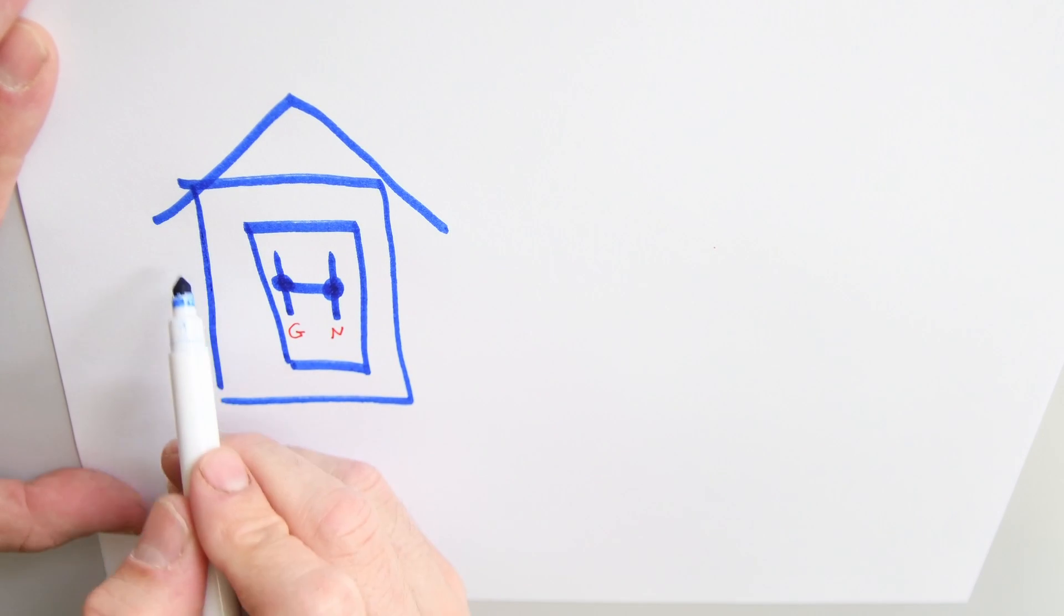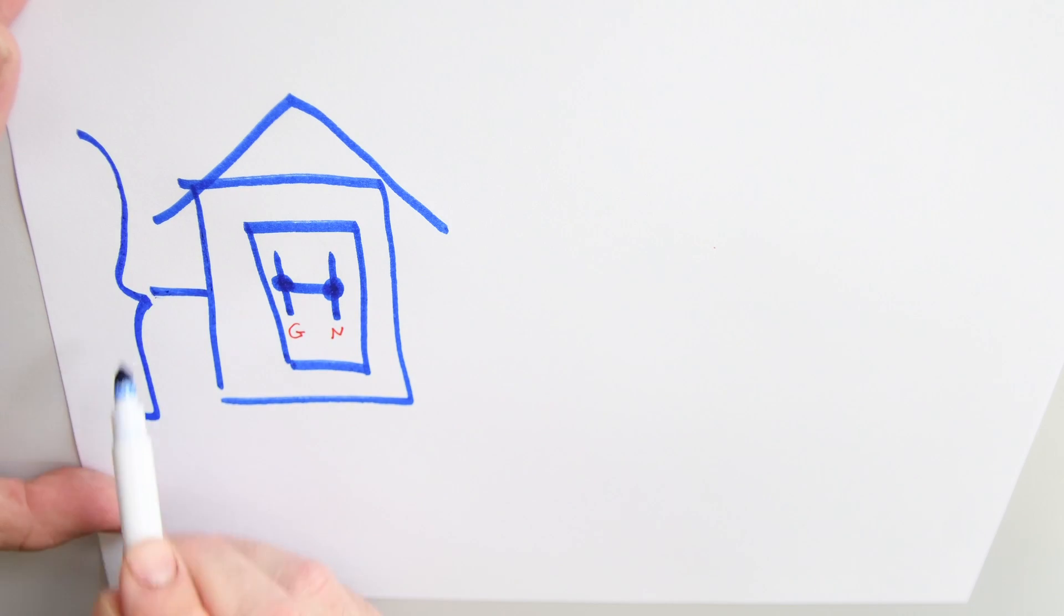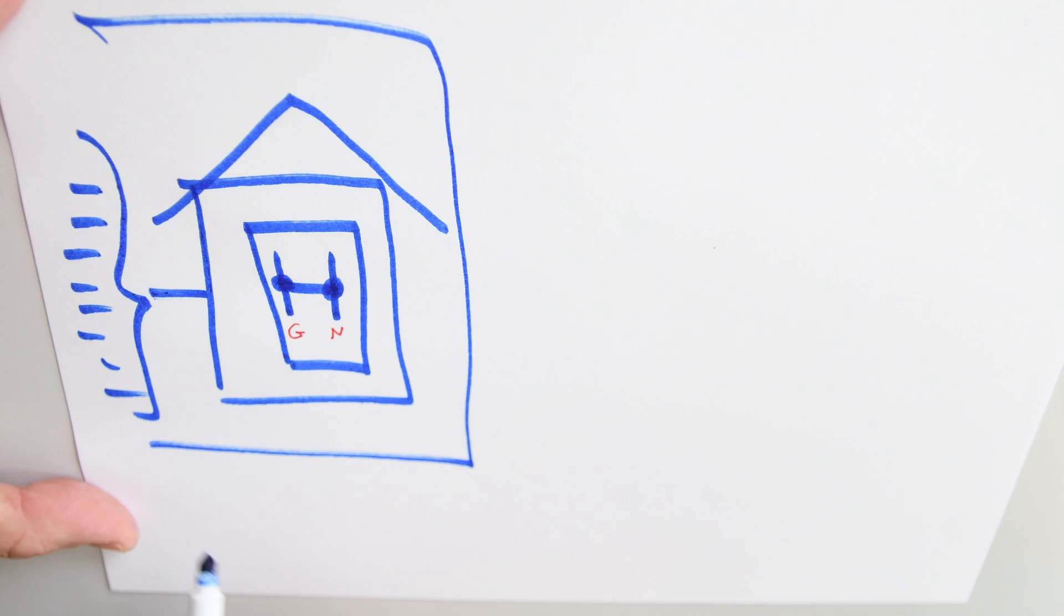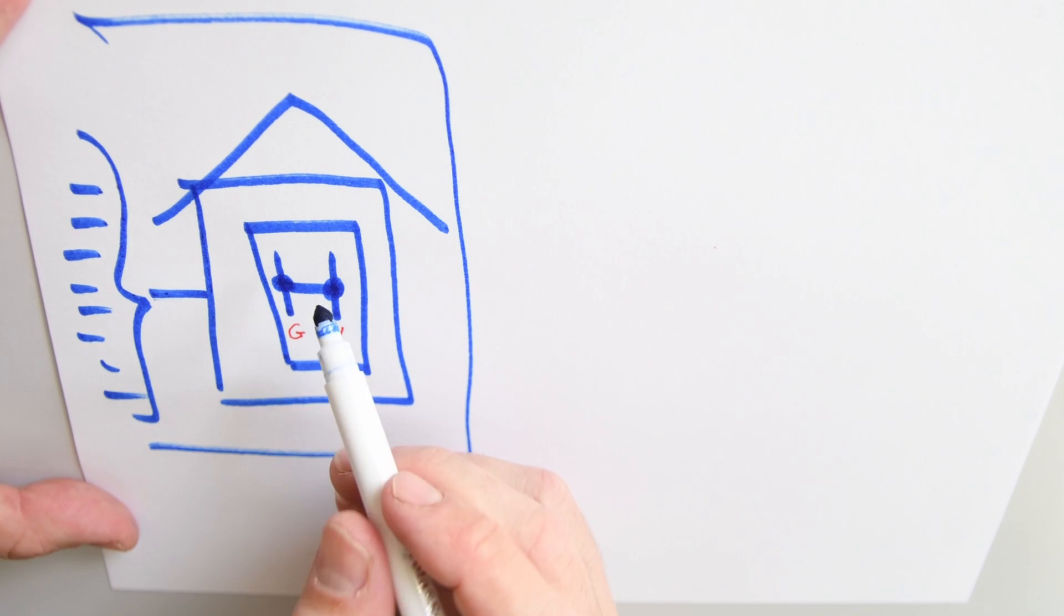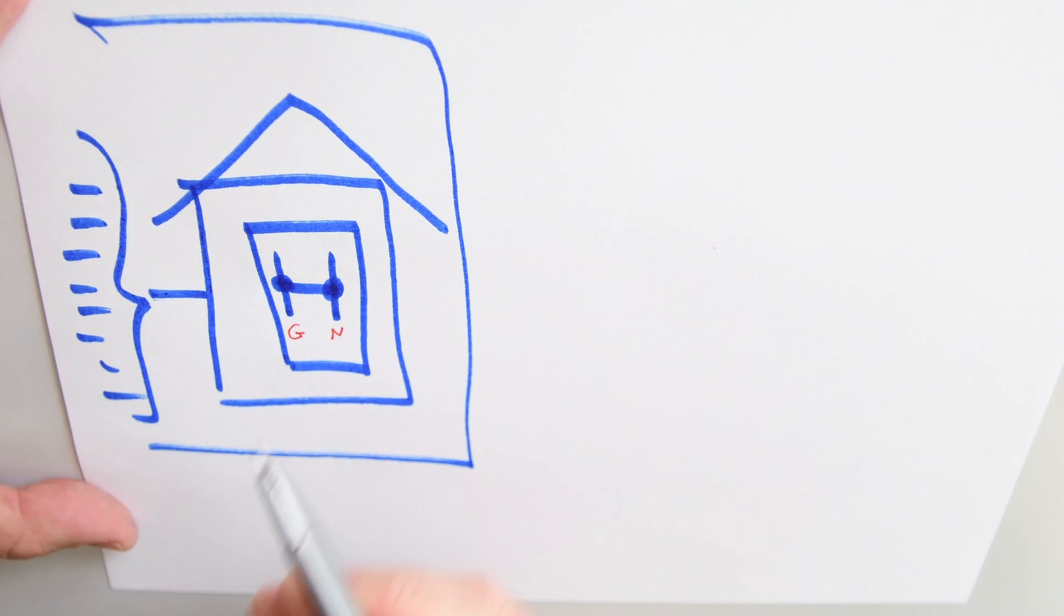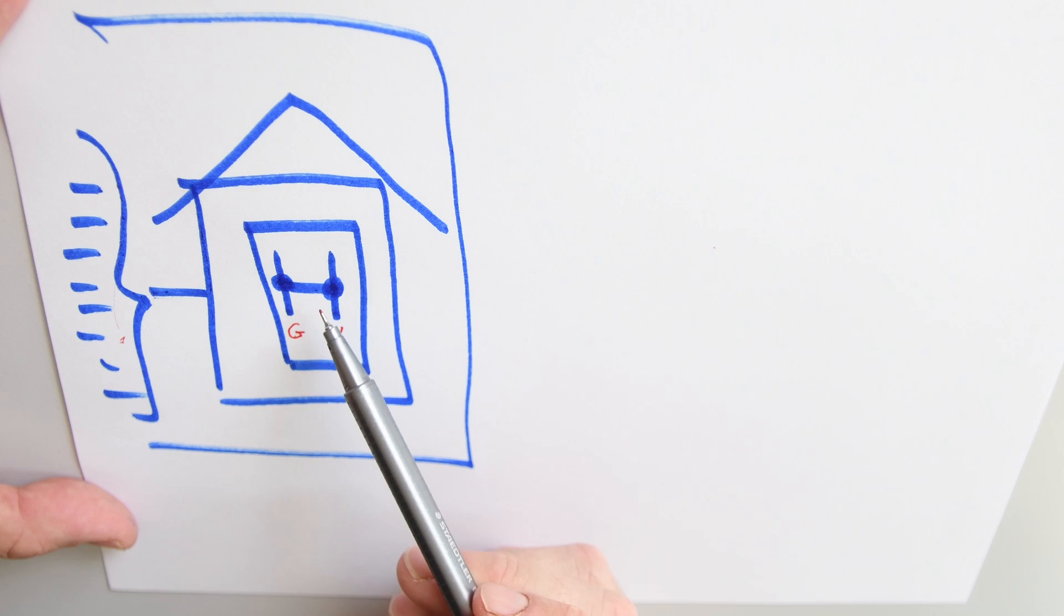So anything that we connect in this system, which is all the appliances inside the house, is going to be complying with the National Electrical Code because there is only one point in which the ground is connected to the neutral. That connection is not happening on any of the appliances, but only here in the breaker panel.